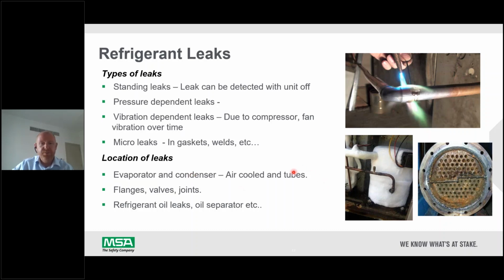And then for shell and tube heat exchangers, which you can see in the photo here, you also have water on one side and refrigerant on the other side. That can lead to corrosion from the water if maintenance doesn't happen, or if there's no glycol or some kind of corrosion inhibitor in the system. There's another photo here of a coil completely freezing up, which can happen in an evaporator as well. The frost or the ice would gradually push a pipe or a flange off, and then we have a complete leak in the system. So maintenance helps reduce these risks, but installing a leak detector at very, very low levels would help identify these leaks at an early stage.